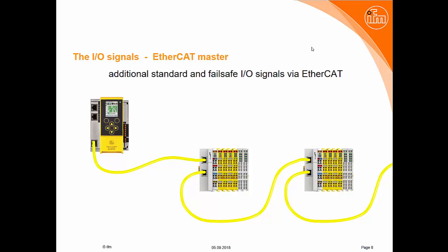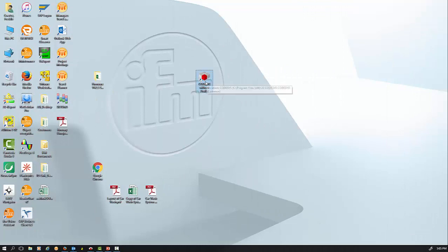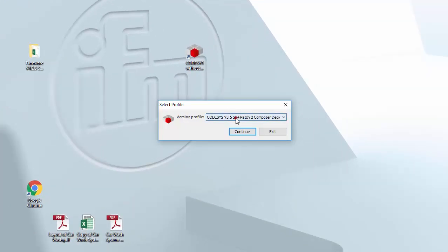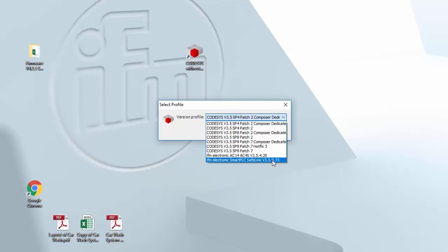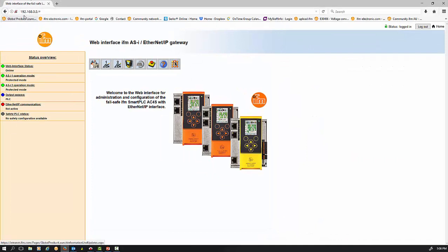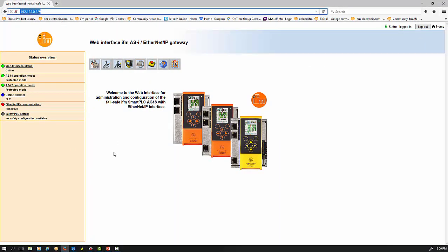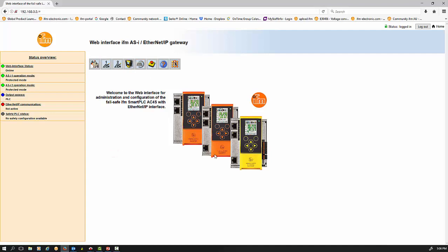I'll go through step by step on CODESYS: how to log on to the PLC, how to start a project, and how to get the EtherCAT system running. First of all, you need to have CODESYS with the SmartPLC SafeLine package. It's a good idea to run in parallel with the web interface — I'm currently logged on to the web interface of the ASI master, where we can see all bits and pieces and especially get the IP address. We're going to start a new project, click on the smart PLC, and call it our test EtherCAT.